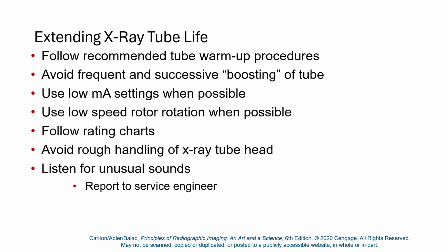Use low mA settings. That's going to save you heat units. Use low speed rotor rotation. Follow the rating charts, which again is going to be controlled by the software. So if the software locks you out, don't try to override that by rebooting the computer. Avoid rough handling of the X-ray tube itself, and listen for unusual sounds.